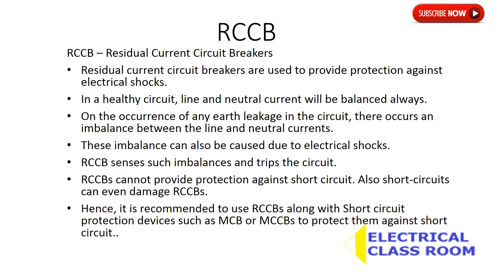Residual Current Circuit Breakers cannot provide protection against short circuit. Also, short circuits can even damage RCCBs. Hence, it is recommended to use residual current circuit breakers along with short circuit protection devices such as MCB or MCCBs to protect them against short circuit.